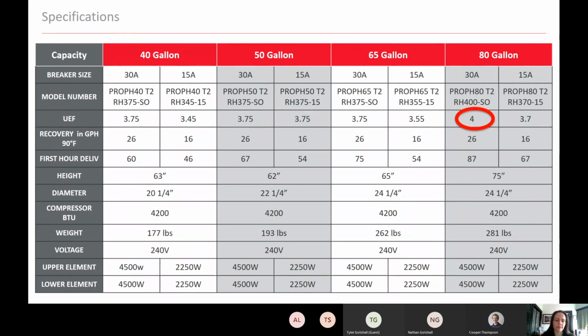So it's very efficient. The other thing to note is the elements. On our 30 amp model, they're 4,500 watt elements, and on our 15 amp, they're 2,250 watt elements. So remember when I talked about the 15 amp model, I said to be cautious to size it appropriately because it offers a slower recovery. Make sure if you use the 15 amp that you look at the first hour ratings, because it's going to be a much lower wattage on those elements.